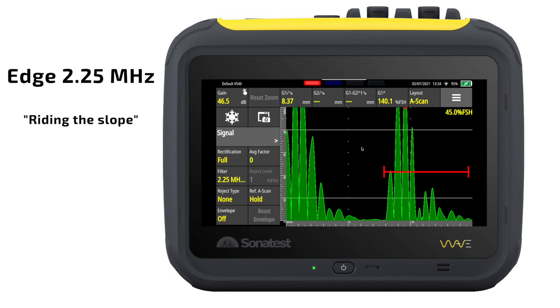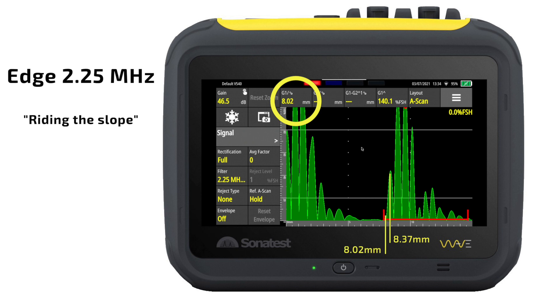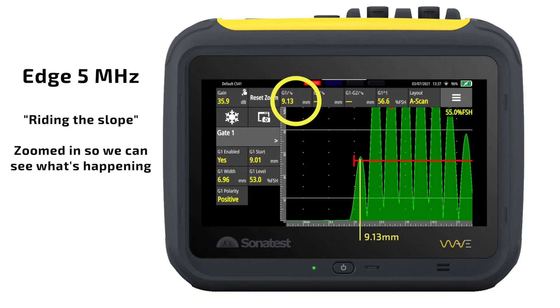Number one is the trigger point, or where the reading is taken. With edge, it will literally ride the slope of the waveform. Here I'm zoomed in on a waveform with the 2¼ MHz transducer. You can see the effect as I lower the gate and the trigger point moves more to the left, reducing the thickness reading from 8.37 to 8.02 — about 0.35 millimeters, or about 15 thou. Higher frequency probes usually work better because your wavelength is shorter and your slope is steeper, which means less of a sound path difference from the top of the lobe to the bottom. With the 5 MHz probe, it changes less than about 0.2 millimeters, which is about half what happened on the 2¼ MHz probe — which makes sense because the 5 MHz probe is about double the frequency.